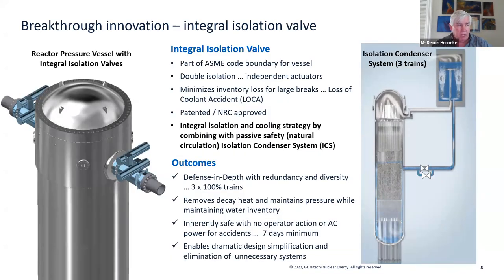Part of the reactor design that's important are these isolation valves. Now, normally in previous designs, isolation valves were containment isolation. They were on the containment boundary. We've moved them in all cases next to the vessel. So there really is very little room between the first valve and the vessel itself. And what we're able to do is move large and medium LOCA events out of the design basis space, but once the valve can isolate, then pretty much most LOCAs are stopped from impacting the safety functions, and so that helps us in overall safety.